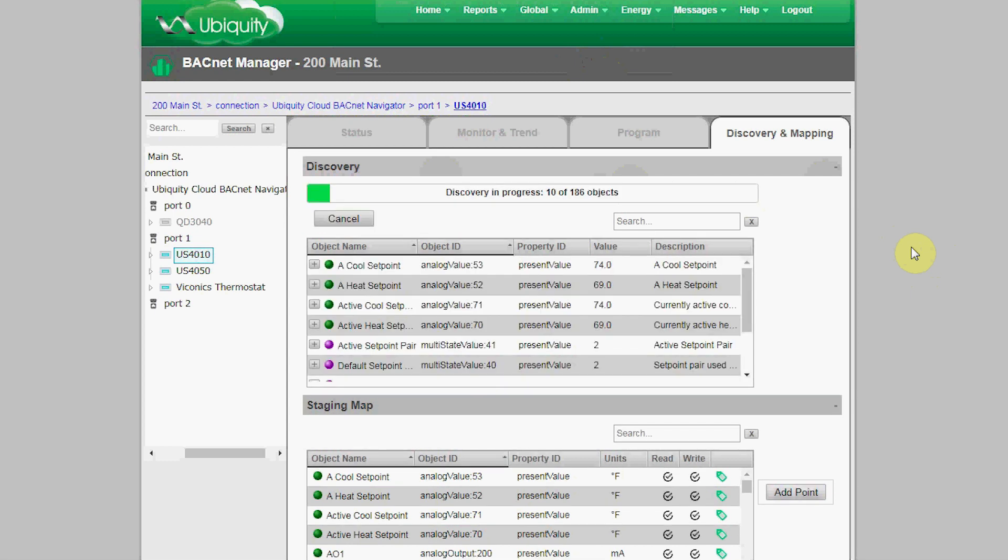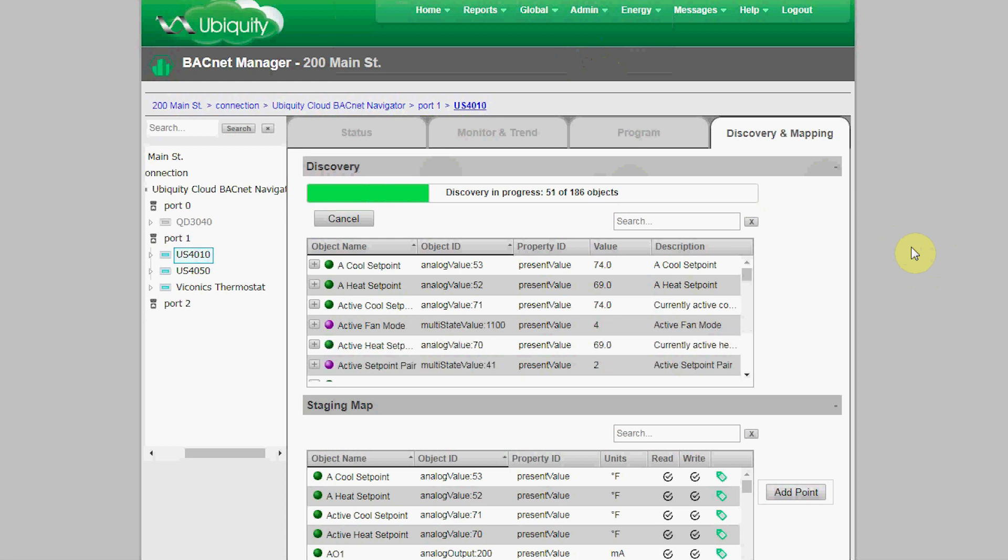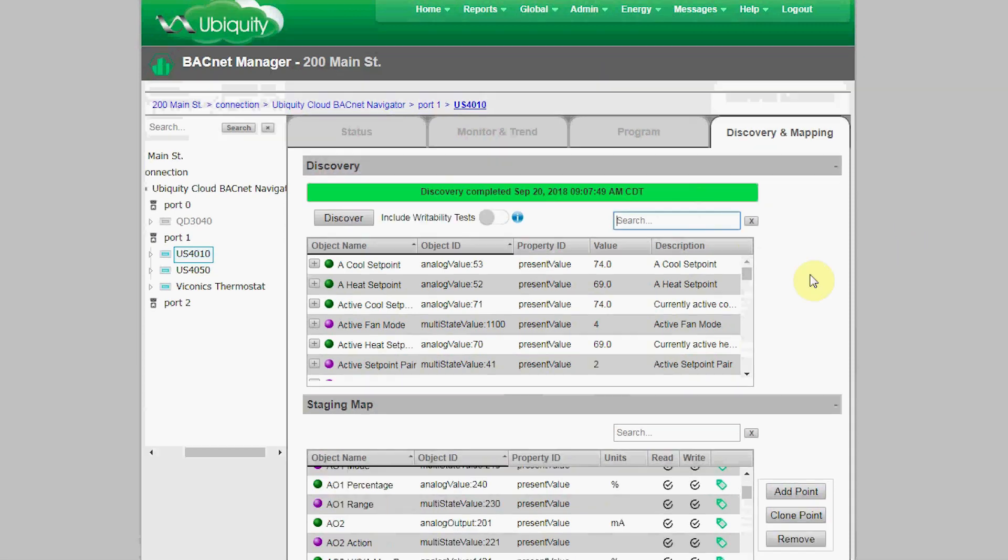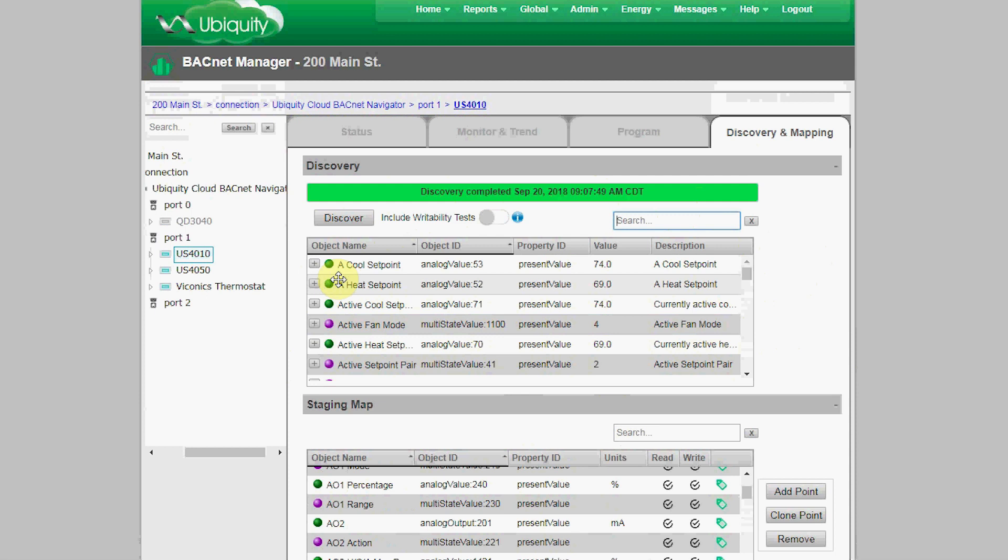In the Discovery section, new discovery of the BACnet objects and properties can be triggered by clicking on the Discover button. This will show the progress of discovery, including how many total objects are on the device as they're being discovered and the progress as they're pushed to the BACnet Manager. Since we already have a discovery file in place from a previous discovery with a timestamp, we'll use that file for this demonstration.